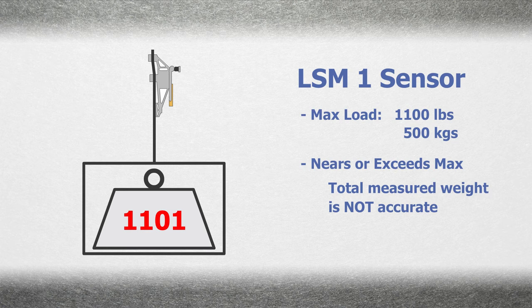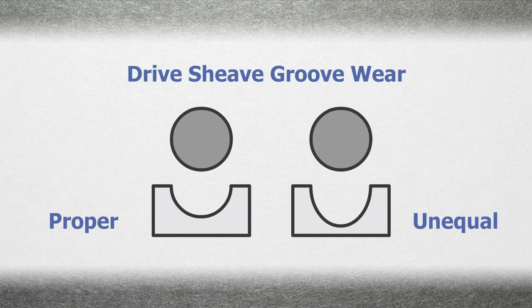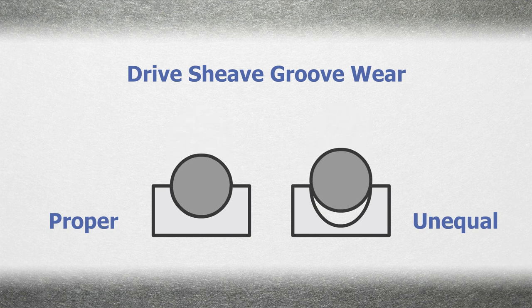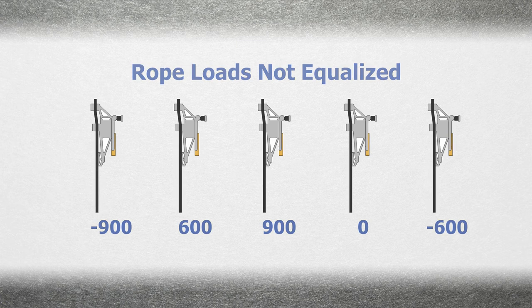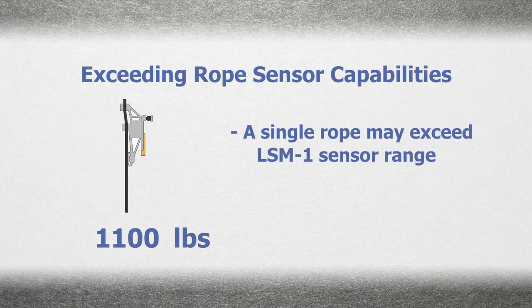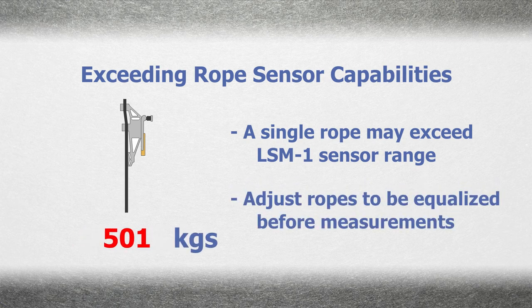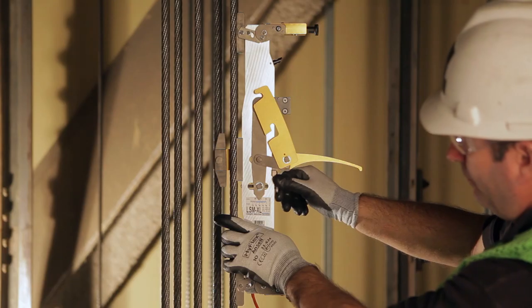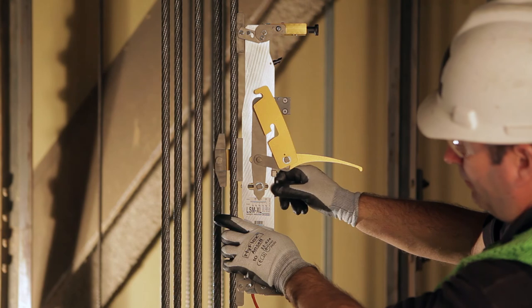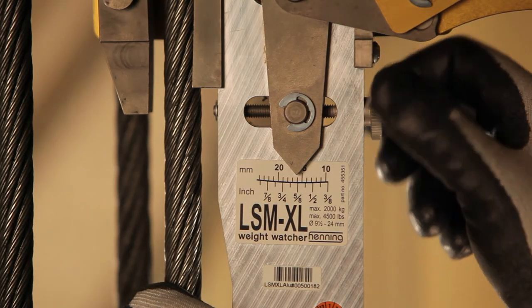This is particularly possible if, for example, you are working with an older system where the grooves in the drive sheave might have worn unequally and rope loads are not equalized. Again, when rope loads are not equalized, the load on a single rope may exceed the 1,100 pound limit for LSM1. If this occurs, the rope load should be equalized prior to the measurement of car weight. In situations where rope loads cannot be equalized, to obtain accurate results with Mobile Weight Watcher, use the LSMXL sensor.